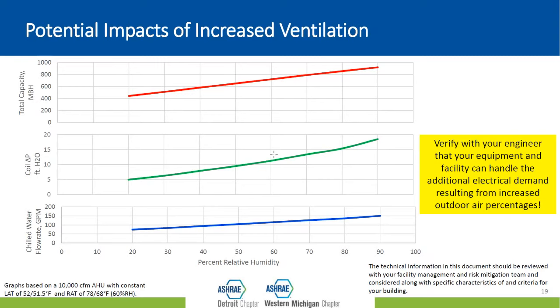right? Additionally, that extra heating, cooling, and moving around of air is going to require additional energy. So we need to be prepared for higher energy bills too. Now, if you've recently done any energy efficiency upgrades at your facility, that's a good thing because those can help offset the increase in energy use you'll see from increased ventilation rates. And your HVAC consultants can help you find out whether or not your existing equipment has the extra capacity that's needed, and then what that additional energy is likely going to cost you. Next slide.